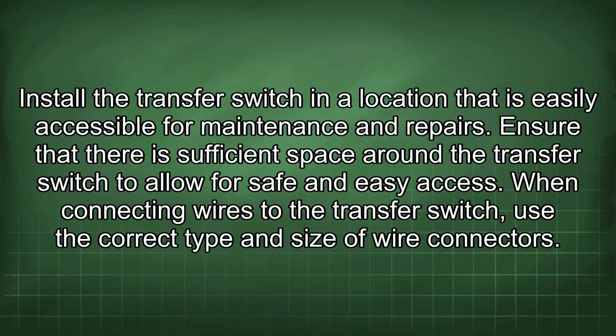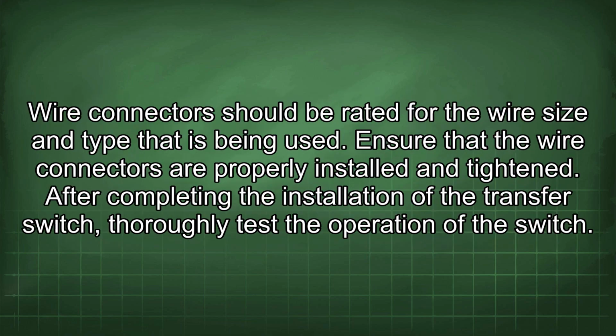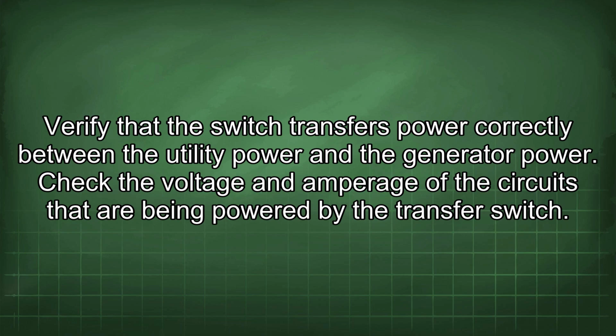When connecting wires to the transfer switch, use the correct type and size of wire connectors. Wire connectors should be rated for the wire size and type that is being used. Ensure that the wire connectors are properly installed and tightened. After completing the installation of the transfer switch, thoroughly test the operation of the switch. Verify that the switch transfers power correctly between the utility power and the generator power. Check the voltage and amperage of the circuits that are being powered by the transfer switch.